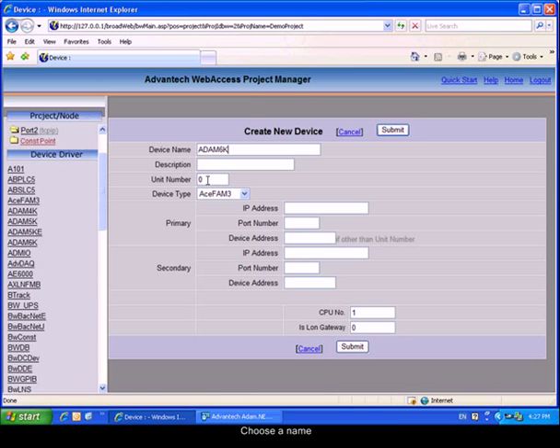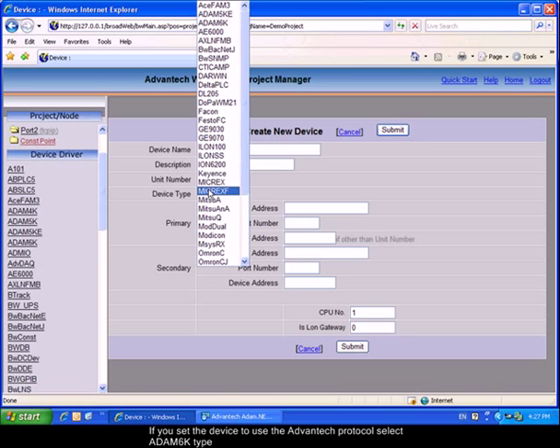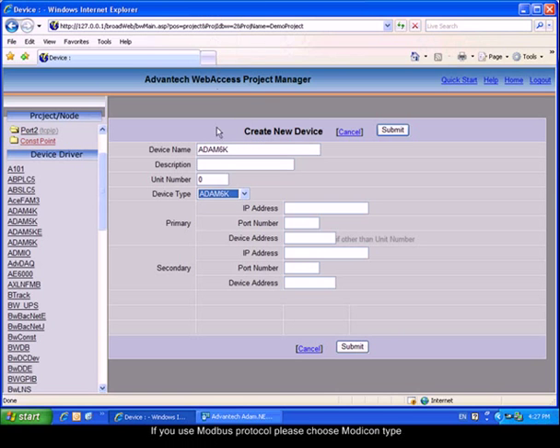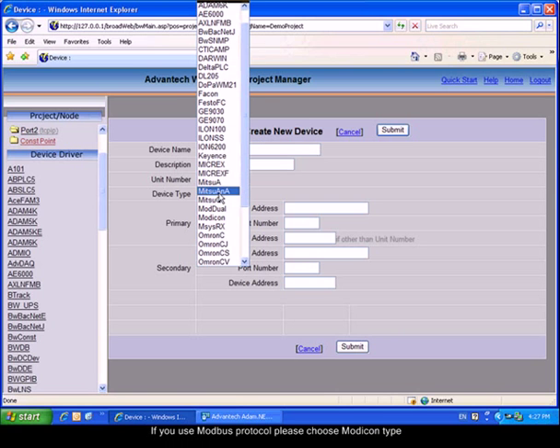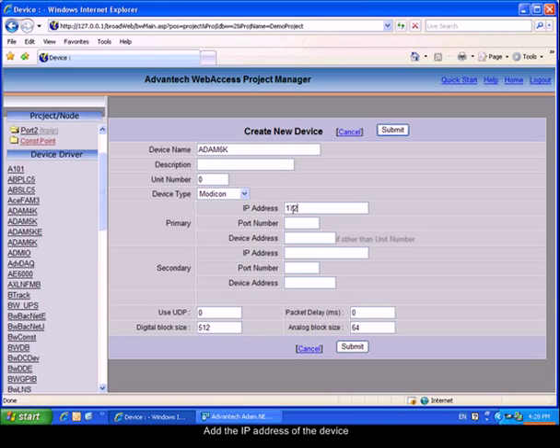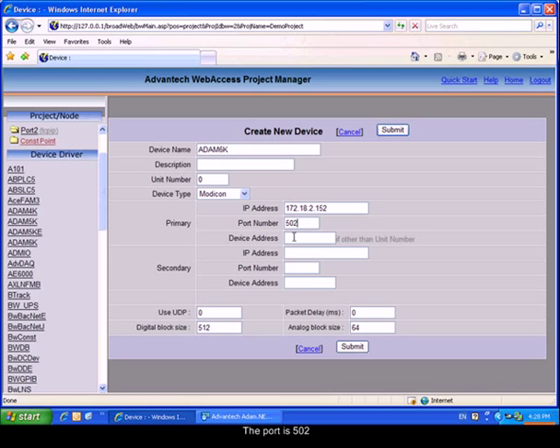Select a device type. It can be ADAM6K if you are using the Advantech protocol or MODBUS if you are using the MODBUS protocol. Please enter the IP address of the module. The port number will always be 502. The device address and unit number is 1.